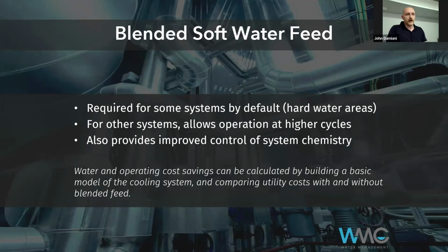areas like Kitchener-Waterloo, Guelph, there's some really high hardness water because you've got municipalities that are fed well water. So the hardness specifically, but other dissolved solids come in at a very high level. So you just naturally cannot cycle that water very high at all. So you often have to partially soften the water in order to just operate it. But in areas where it's not strictly required, it can be just an improvement on the engineering side.